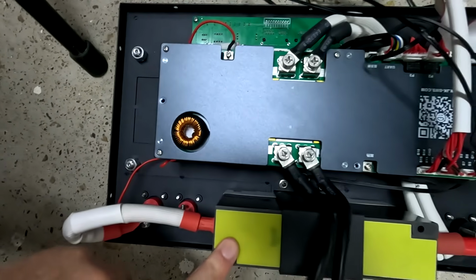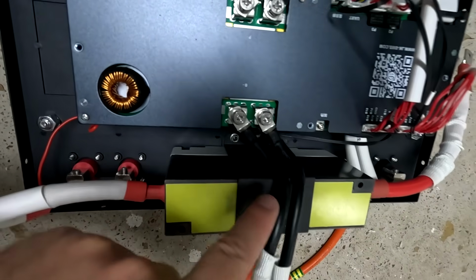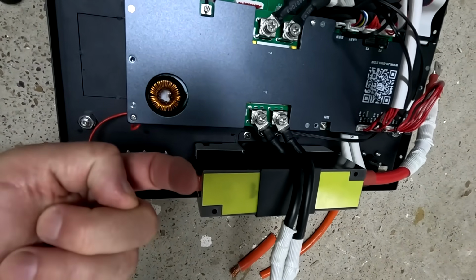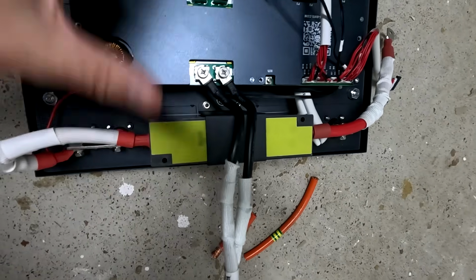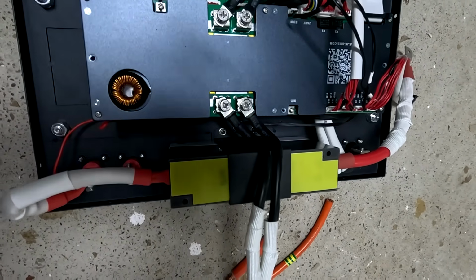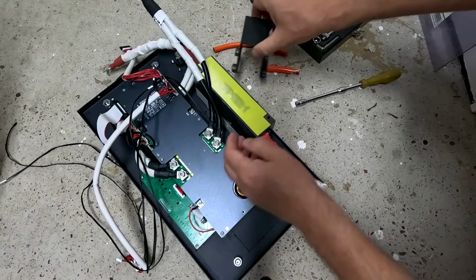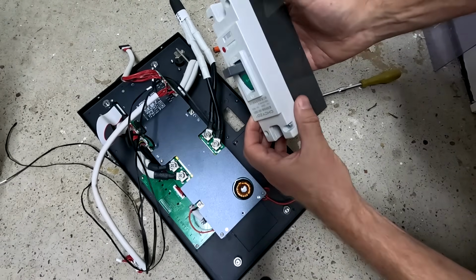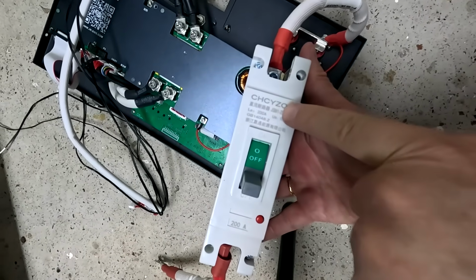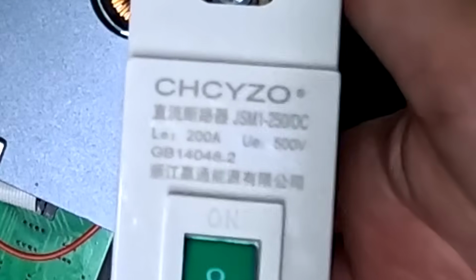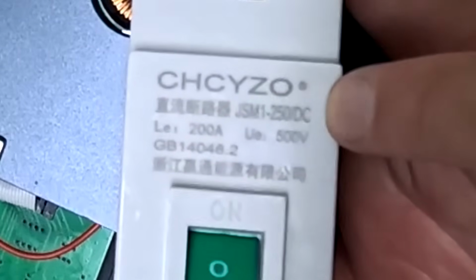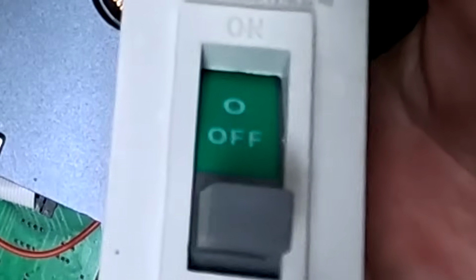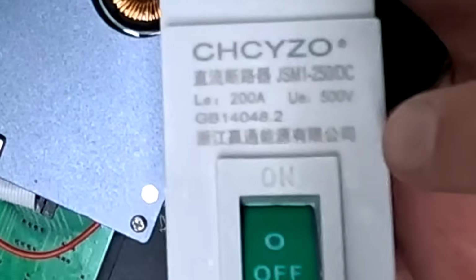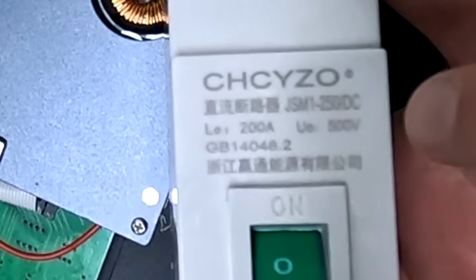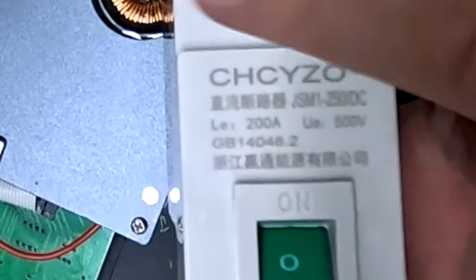We probably have a 250 amp circuit breaker, but I cannot see that. I have to take off the whole circuit breaker. Maybe there's something on the other side, but here no markings, no labels, no branding, nothing. Okay, so this is the bracket. And now it comes off. Okay, this is the usual CHCYZO. It's a 200 amp circuit breaker actually, thank you. 250 volt DC. 200 amps it says here as well. It doesn't say anything about the breaking capacity. So I'm not sure if this circuit breaker is rated for this battery.